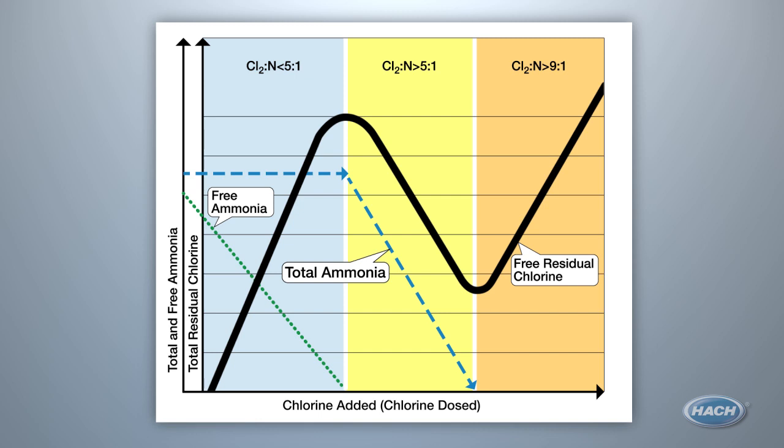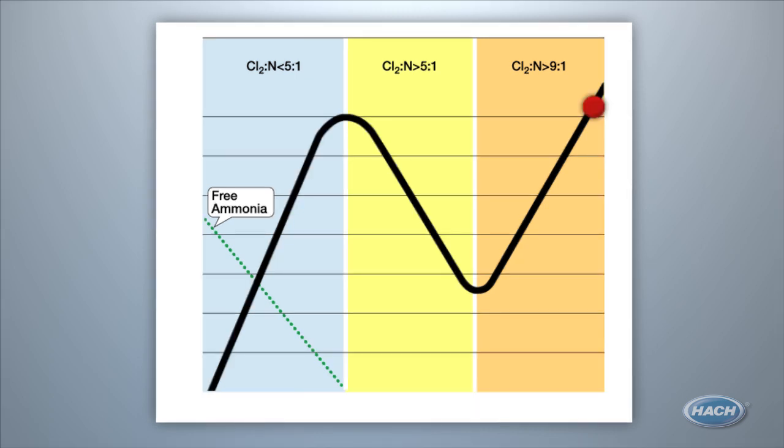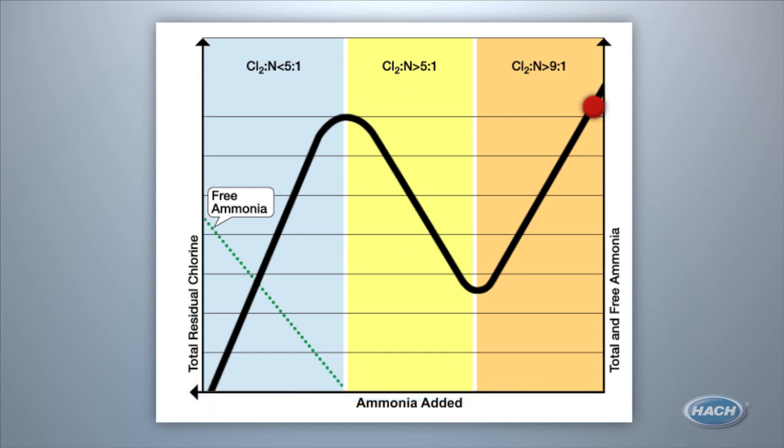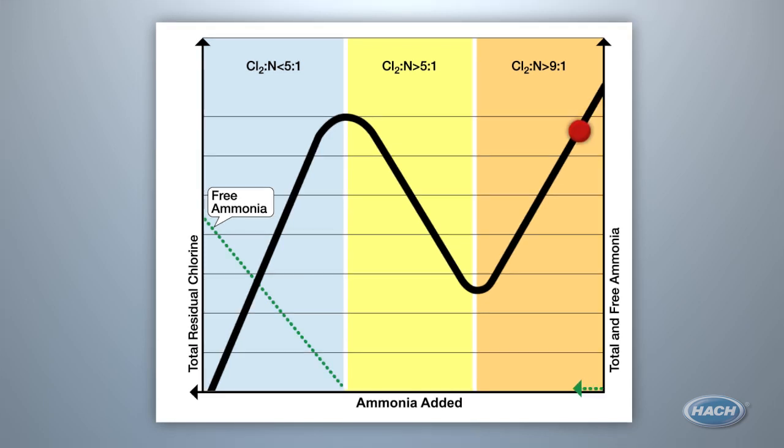So does this change if your utility adds ammonia to water that has already been chlorinated, as many do? The concepts all stay the same. You just move backwards along the line. Ammonia is added to the chlorinated water just prior to entrance into the distribution system. The dose is increased until a small trace of free ammonia is detected, ensuring you are in zone one and maximum monochloramine residual has been reached.